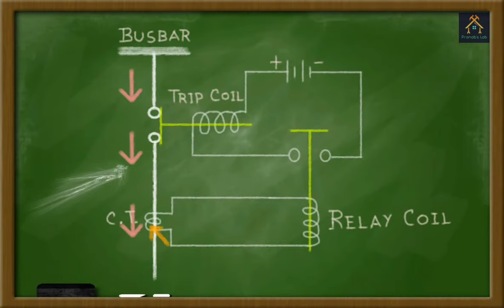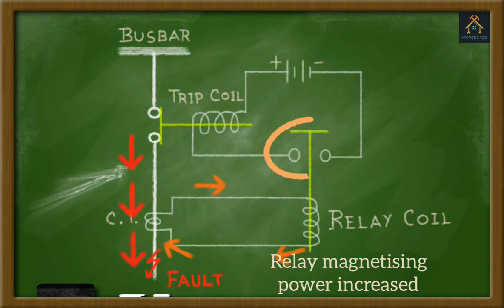Now, let's assume a fault is occurred in the line. As a result, a huge amount of current will be flowed from the bus bar to the line. And according to the CT ratio, it will also carry a large amount of current from the CT to the relay coil. With the increase of the CT current, the magnetizing power of the relay is also increased and it attracts the plunger.